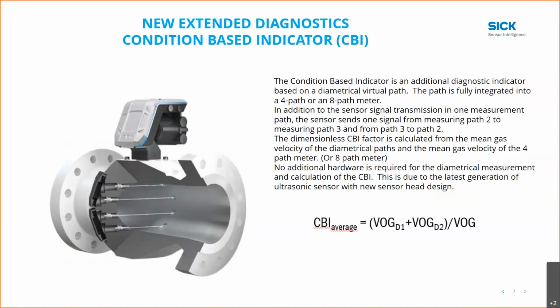Now, if we look at a 4-path meter in this example, as you know, here is one pair of transducers. Here's a second pair of transducers, third and fourth. So this is a 4-path meter. We are sending sound waves downstream and upstream between this pair of transducers, and we're measuring the transit times downstream and measuring the transit times upstream. And we're calculating our average velocity on the 4-path.